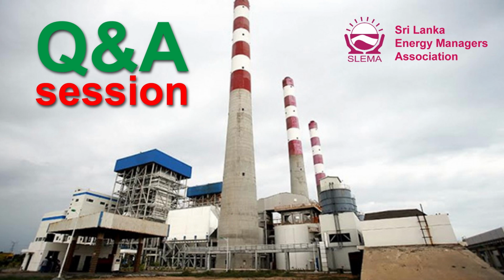What is the time taken for a hot start of the power plant? It depends upon the condition of the power plant. For a hot start, it takes a minimum amount of time, maybe 5 to 6 hours, because the temperatures of all the auxiliary things have already reached the required levels. Most of the expansion of the turbine, the boiler, and the steam drum is already there. That's why we can start the power plant very quickly.